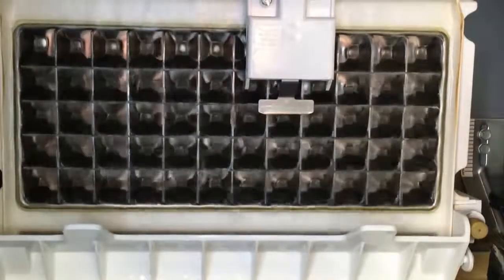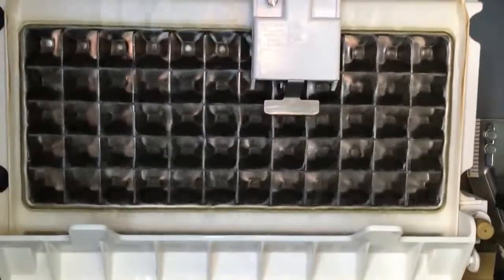So I measured a bunch of temperatures originally. Let me go back to that circuit board. The green light means that... oh, the red light just went on. No, the red light just went off again. Okay. The green light means that there is no connection between the ice and the sensor, so the ice thickness is still building up.